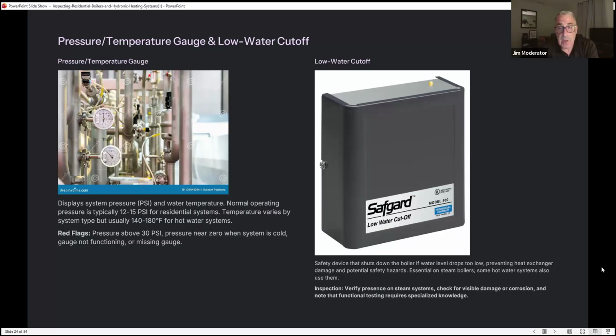And you're going to see your safeguard, the low water cutoff, a safety device that shuts down the boiler if the water level drops too low, preventing heat exchanger damage or potential safety hazards. Essential on steam boilers. Some hot water systems also use them. For the inspection, you want to verify the presence on steam systems, check for visible damage or corrosion, and note that functional testing requires specialized knowledge. So you're not going to test these systems, but you want to make sure that they're there.